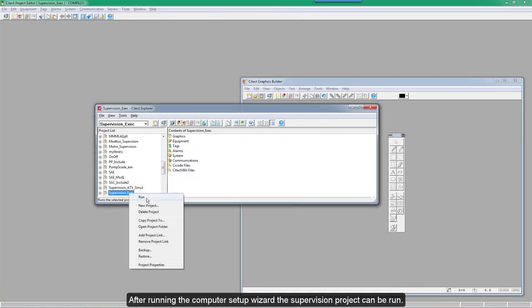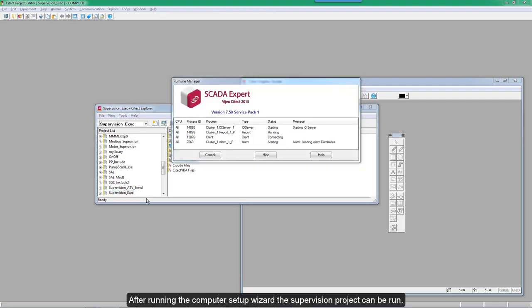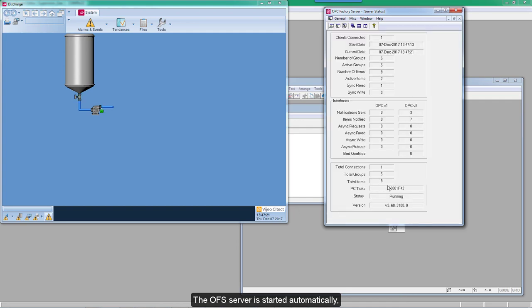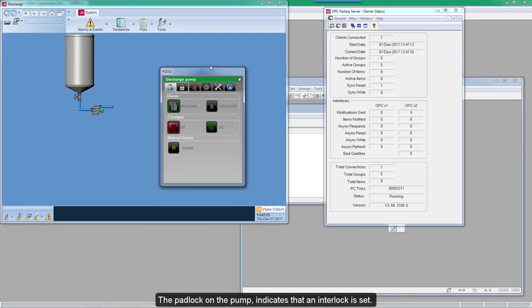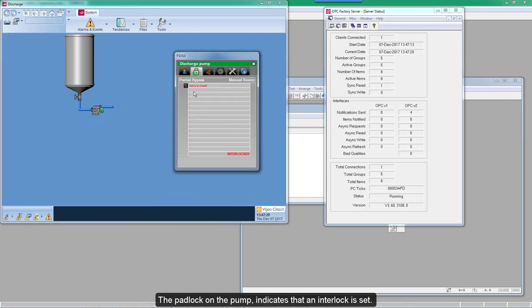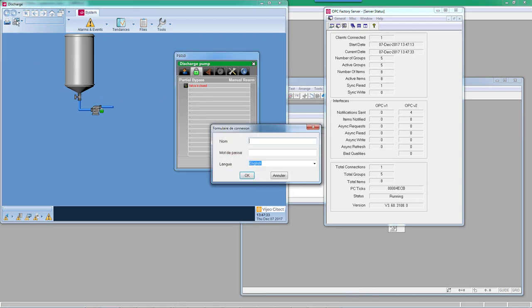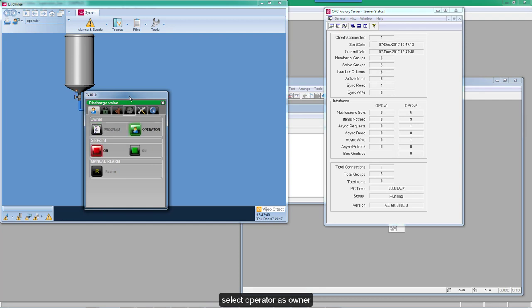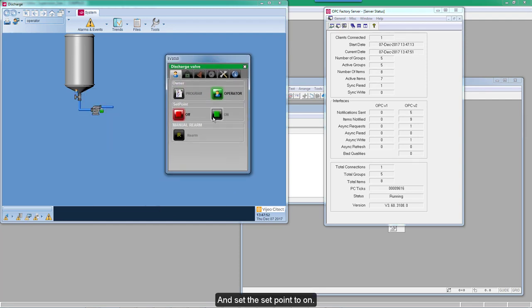After running the computer setup wizard to set the computer parameters, the supervision project can be run. The OFS server is started automatically. The padlock on the pump indicates that an interlock is set. The interlock condition is shown in the padlock tab in the pump faceplate. To open the valve, the operator must be logged in. Then click on the valve, select Operator as owner, and set the setpoint to ON. The valve opens and the interlock disappears.